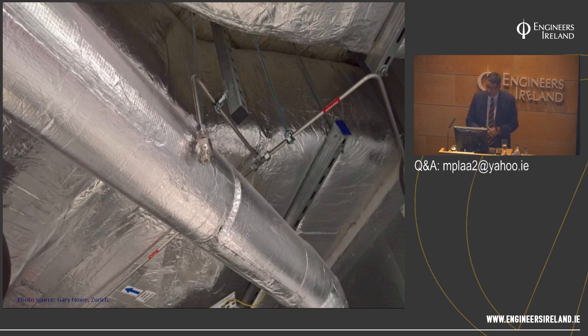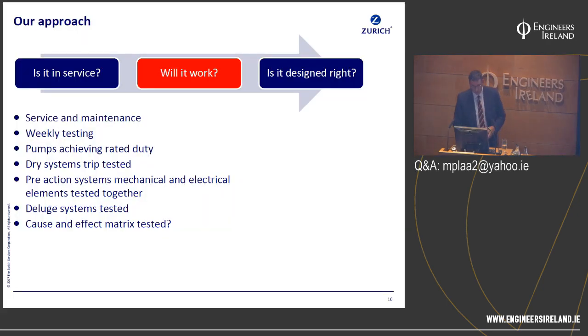And by the way, the other crime in that one is that the pipework in the machinery plant room, you could have swung from it, because it was like a washing line inside the machinery space. And when you grabbed hold of the pipework, it made a tune as you pulled it. So will it work? And it's really important. This applies, is it in service, will it work? Equally applies to all forms of fire protection, but I'm predominantly concentrating here on sprinklers and water mist.